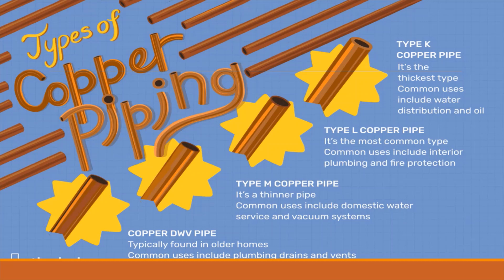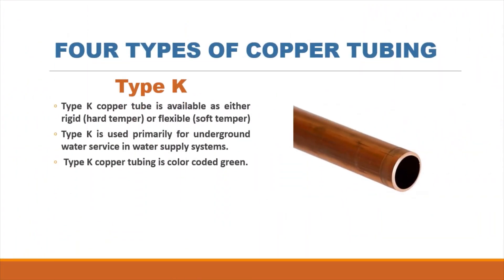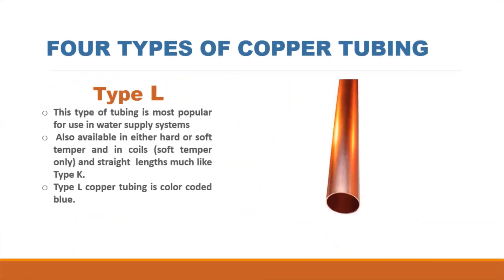There are four types of copper tubing: Type K, Type L, Type M, and DWV. Type K copper tube is available as either rigid or flexible and is used primarily for underground water service in water supply systems. Type L is the most popular for use in water supply systems, also available in either hard or soft temper, in coils and straight lengths much like Type K.